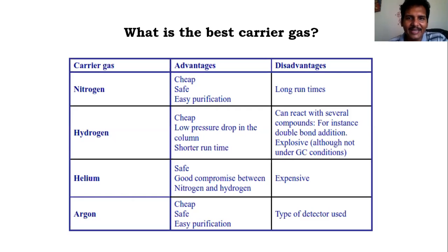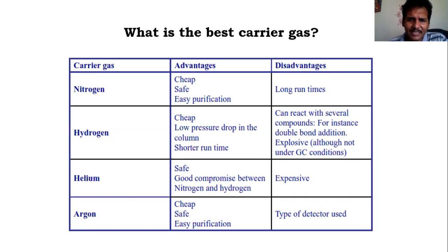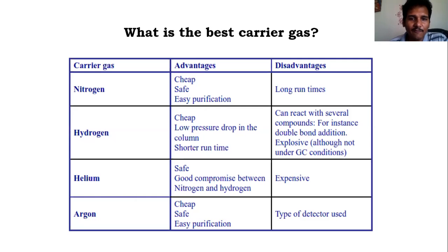Common carrier gases include nitrogen — cheap, safe, easy to purify, but slow through the column — and hydrogen or helium, which are faster but more expensive. Hydrogen can react with several compounds and may be explosive, so each gas has constraints. The choice of carrier gas depends on the specific requirements of the analysis.